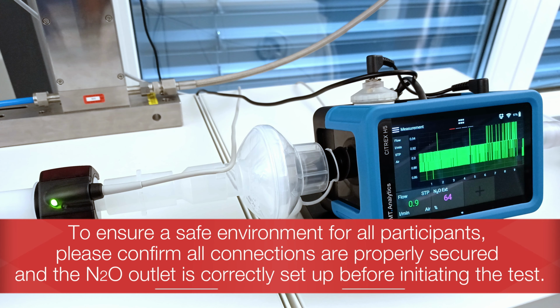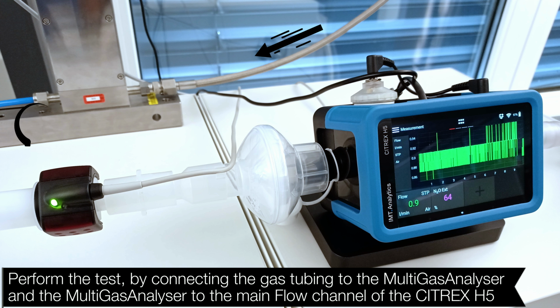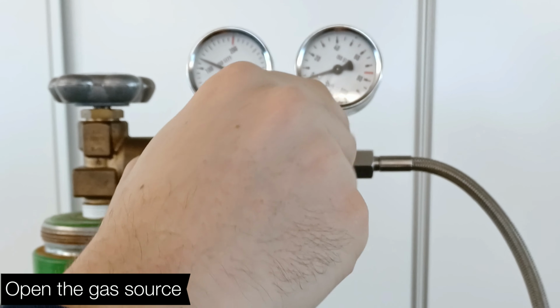To ensure a safe environment for all participants, please confirm all connections are properly secured and the nitrous oxide outlet is correctly set up before initiating the test. Perform the test by connecting the gas tubing to the MultiGasAnalyser and the MultiGasAnalyser to the main flow channel of the CITREX H5. Open the gas source.